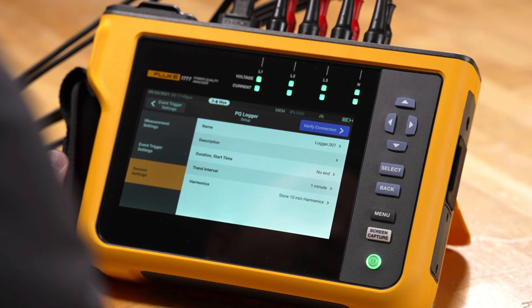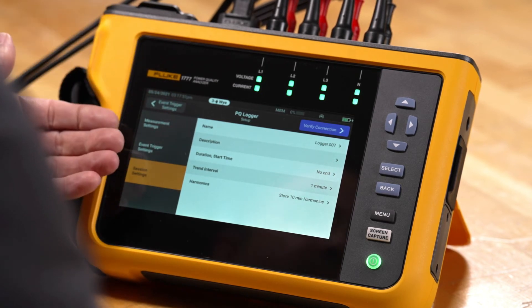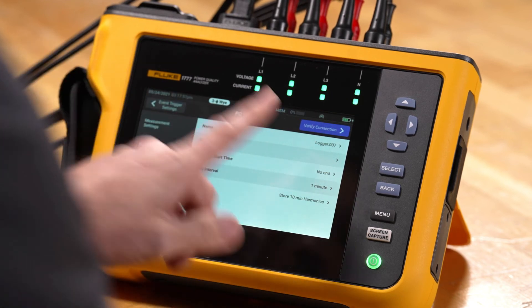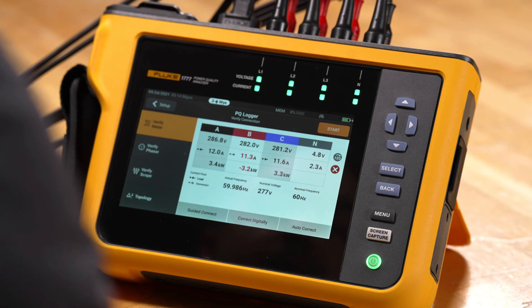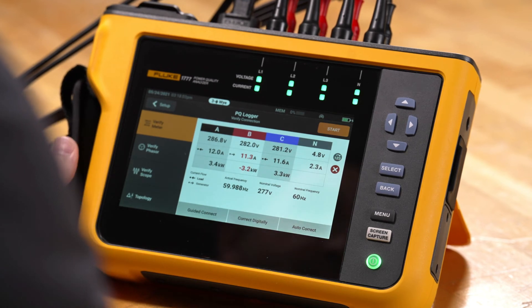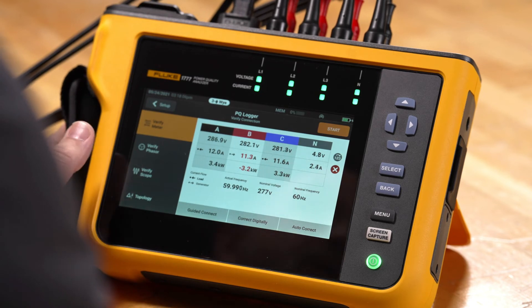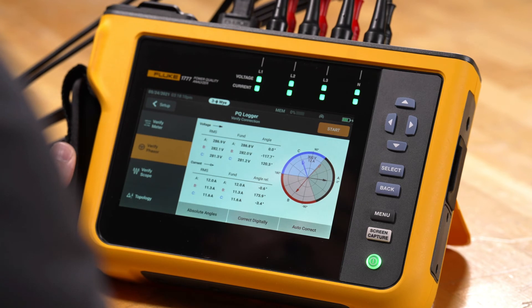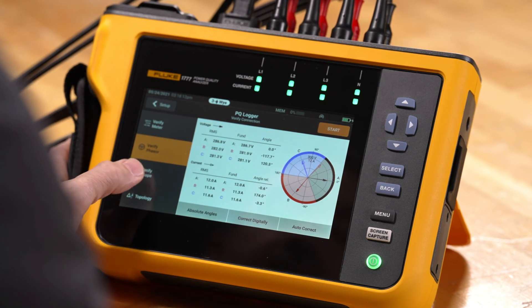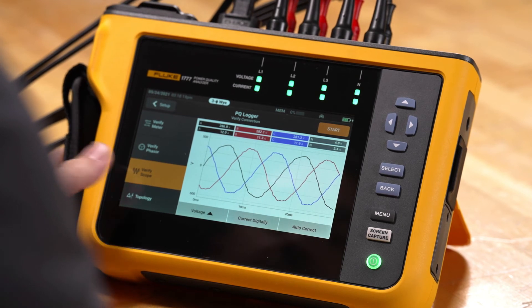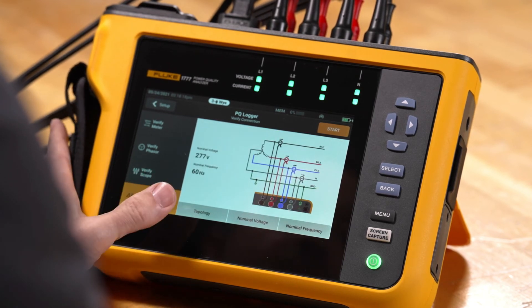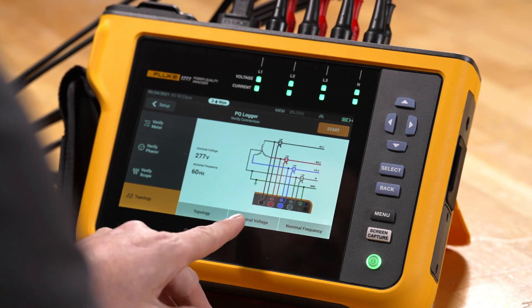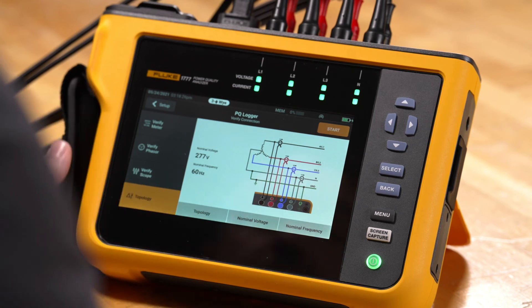The next step is to verify configuration. Once we've verified our settings are correct, we go to Verify Connection on the screen and tap it. That puts us into a screen showing our live active voltages, our power, and our current numbers. We can click Verify Phasor to get our vector diagram, go to Verify Scope to look at waveform data, and also go to the topology where we can change from a Y to delta configuration. We can also change the nominal voltage and nominal frequency from here.